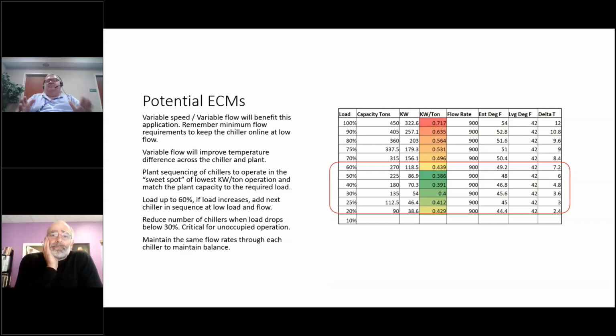That's why I'm using this as an example. What is wrong with this assumption is that it's a constant flow rate. That's where we're pointing to an ECM, where you vary the flow to improve the delta T. And I know, John, you've asked me before, is it better to run 2 pumps at 50% or 1 pump at 100%? In this case, it's better to start another machine to get better performance at a lower level and improve your delta T, because now I'm going to start a second machine and a second pump running at 50% to get into that sweet spot on this chiller.